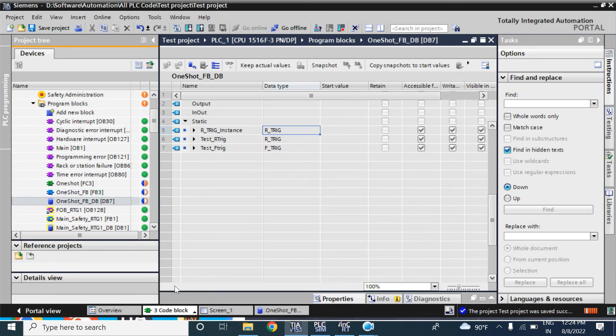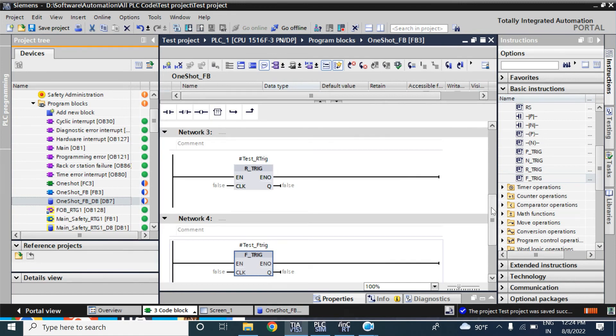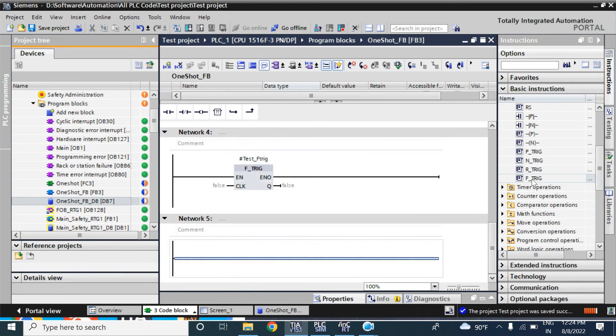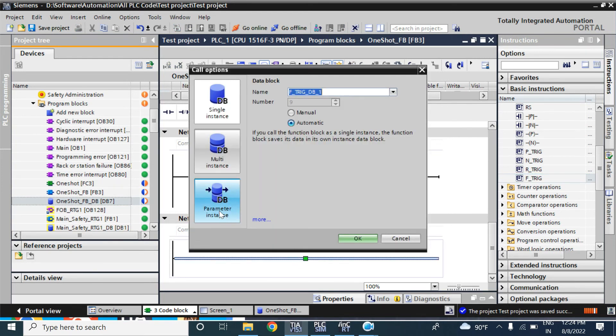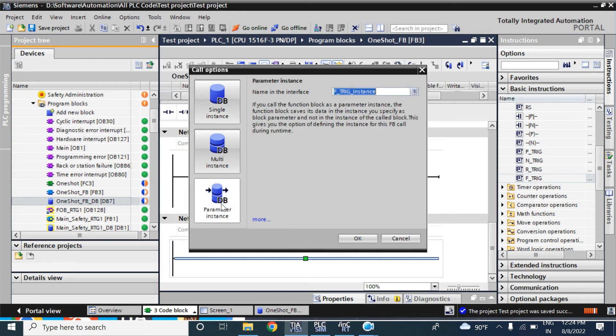Now go back again to oneshotfb. Here I will add R_TRIG or F_TRIG. If you select the parameter instance — if you select the R_TRIG as a parameter instance — then your data will save here. If you call the function block as a parameter instance, the function block saves its data in the instance you specify as a block parameter, not in the instance block of the calling block.